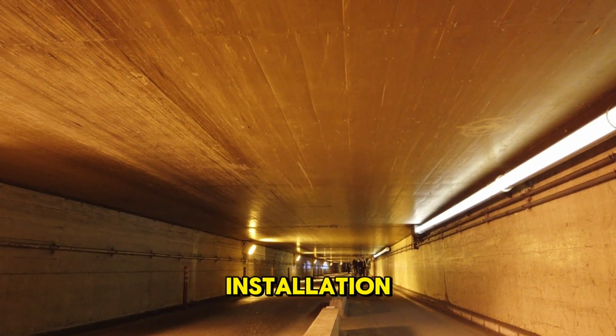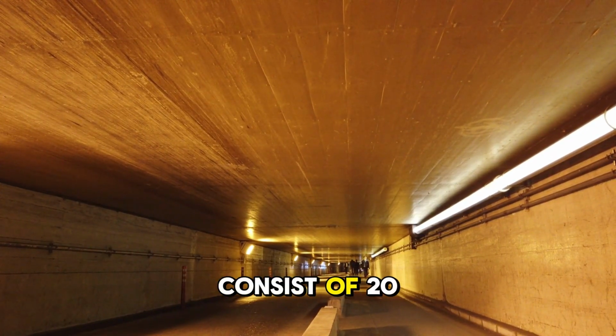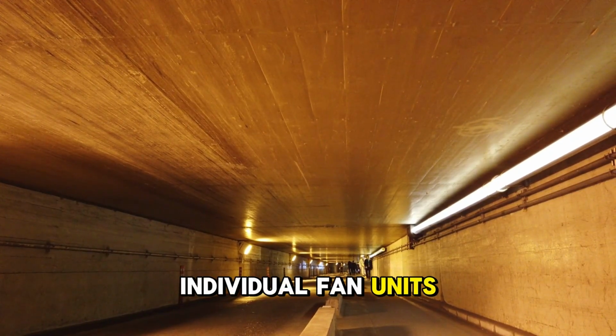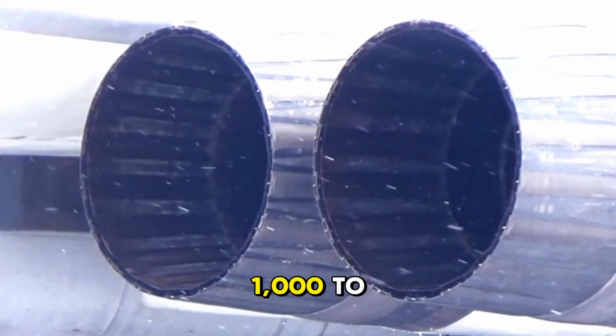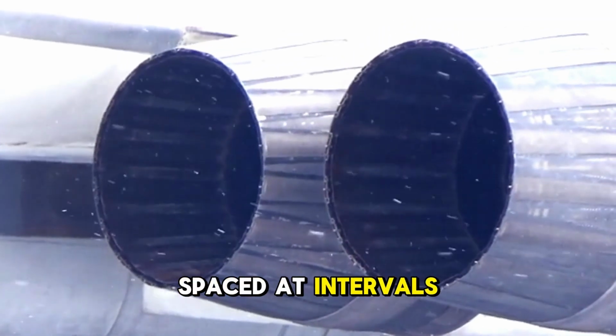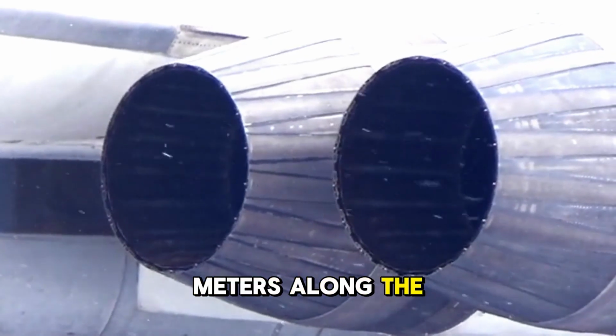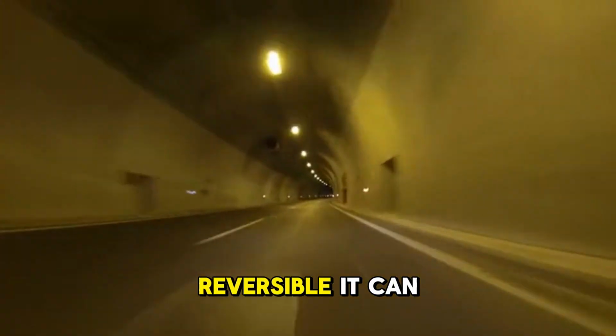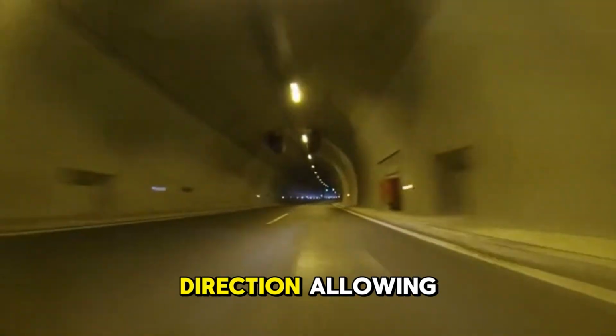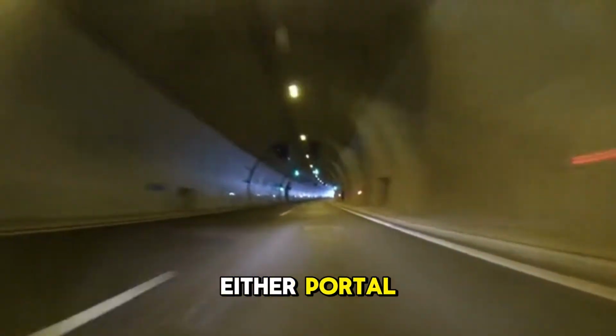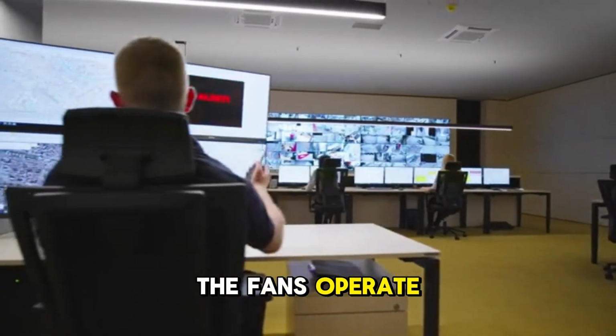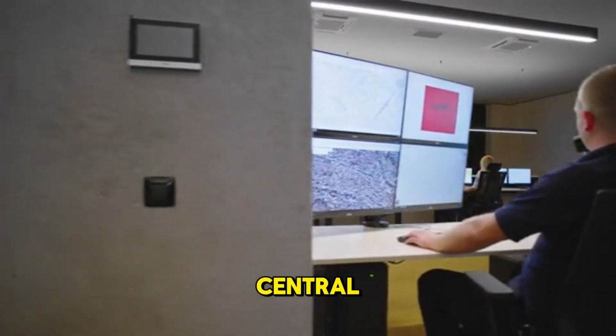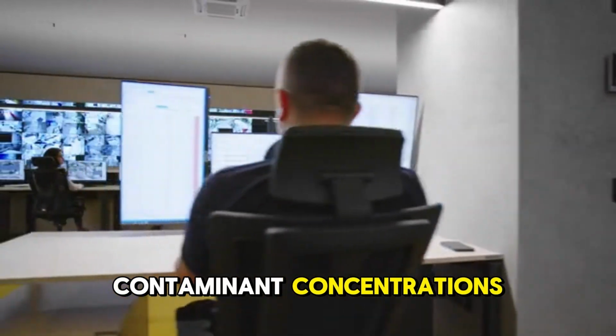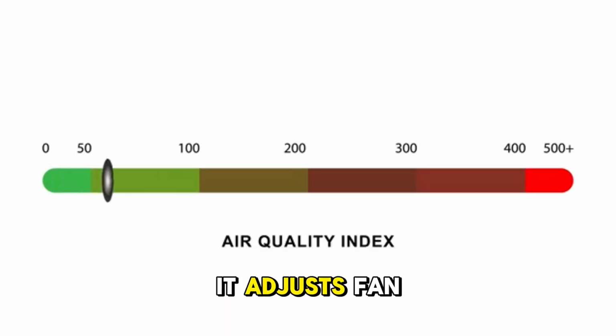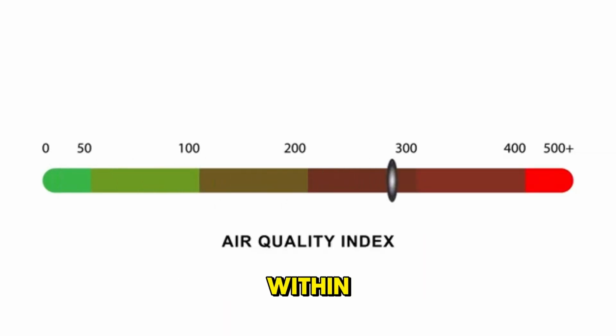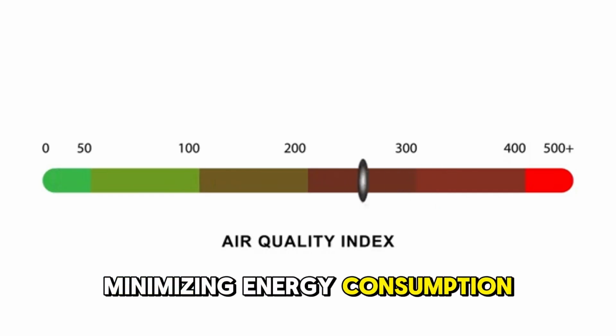A jet fan installation for a typical two-lane tunnel might consist of 20 to 40 individual fan units. Each unit produces a thrust of 1,000 to 2,000 newtons, spaced at intervals of 80 to 120 meters along the ceiling. Each fan is reversible. It can thrust in either direction, allowing the system to push air toward either portal depending on traffic. The fans operate at variable speeds, controlled by a central management system that monitors contaminant concentrations and visibility. It adjusts fan output to maintain air quality within specified limits while minimizing energy consumption.